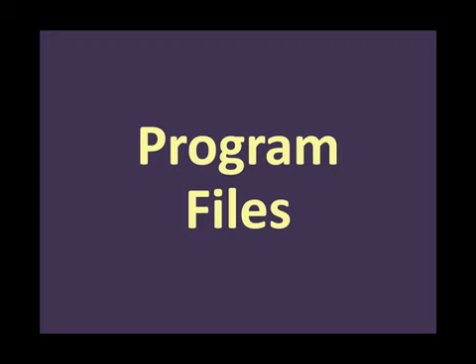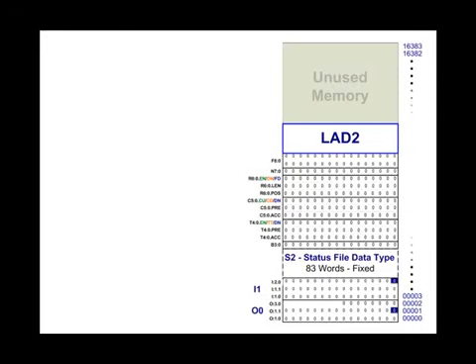Now comes the moment we have all been waiting for: the program files, the relay ladder logic. We are going to cross the line that separates the data files from the program files. For this family of processors, the program files that store the sequential logical instructions are labeled Ladder 2 through Ladder 255. Ladder 2 is unique in that it always executes automatically whenever the processor is in the run or remote run modes. Ladder 3 through 255 require a special instruction to jump from Ladder 2 to their location in memory and execute them, because they are actually subroutines.